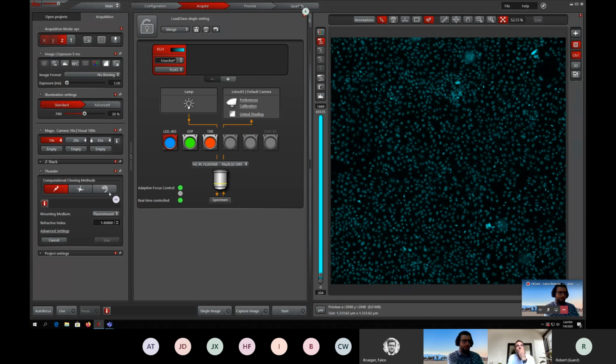Okay. And here you have this zebrafish embryo again, large volume computational clearing. If you activate this, it tells you you're using a single plane. Keep in mind, large volume computational clearing combines computational clearing, so the removal of background light, and 3D deconvolution. And 3D means you need a Z-stack for that. Okay, that's why here you could do it, but of course it's then just computational clearing.